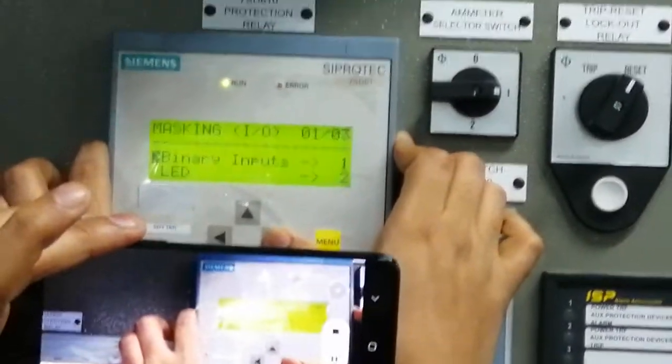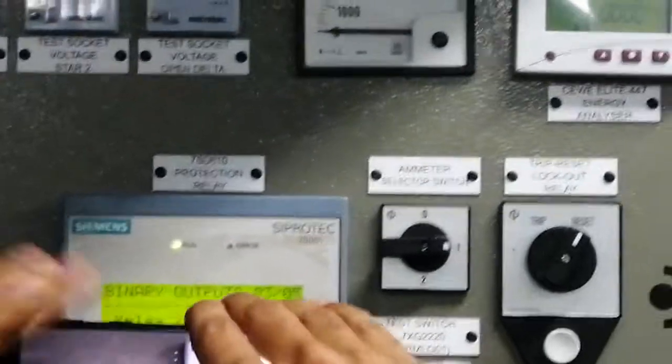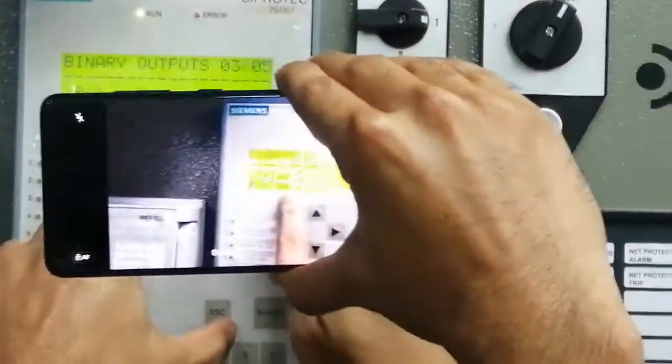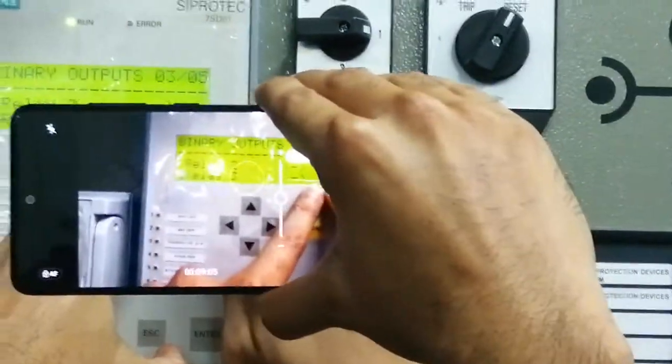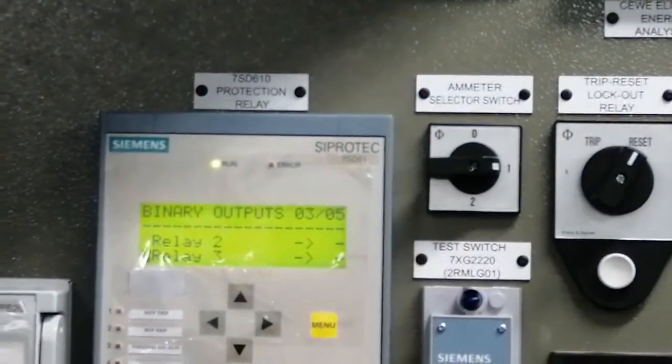So we'll also show you the signals. Here is the binary output of the 11 kV SIPROTEC relay that is going to the ABB. So it is BO3. As you can see, the SIPROTEC relay output BO3 is 0. This is the output of this SIPROTEC relay to the ABB relay. So please show in the ABB relay which was that signal. X20. So as you can see, X20 input 1, it's false. Okay, so we have checked this, and now we will actually try it.